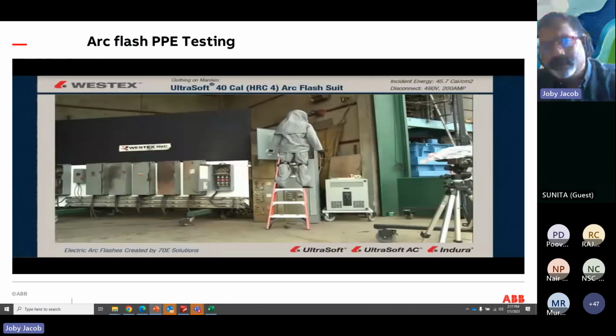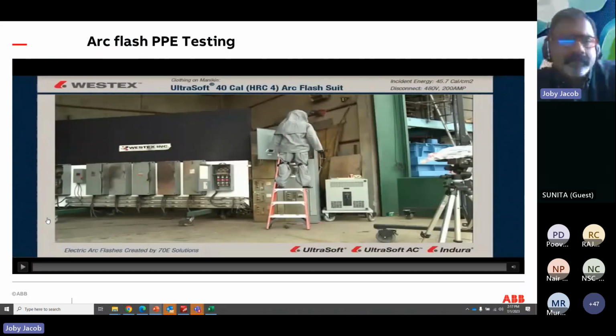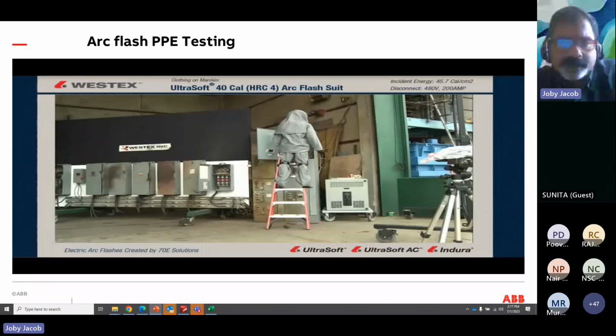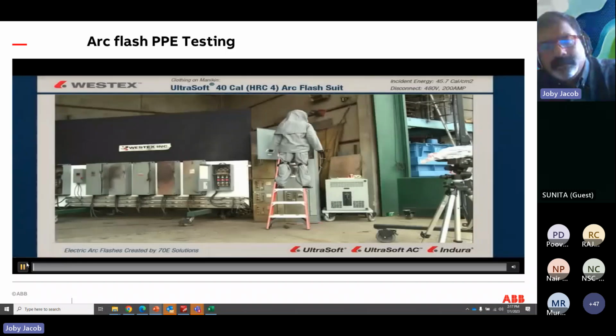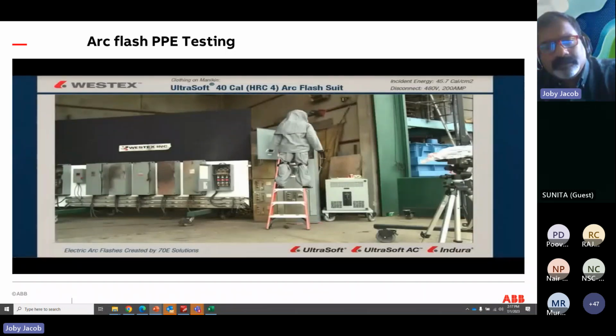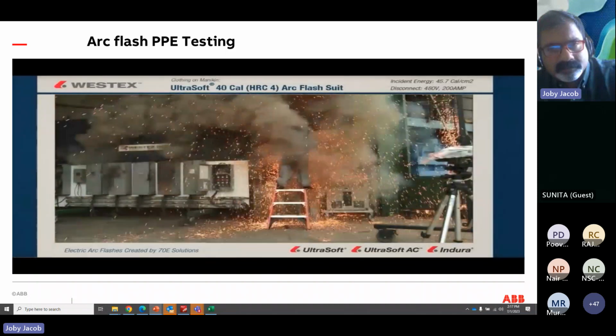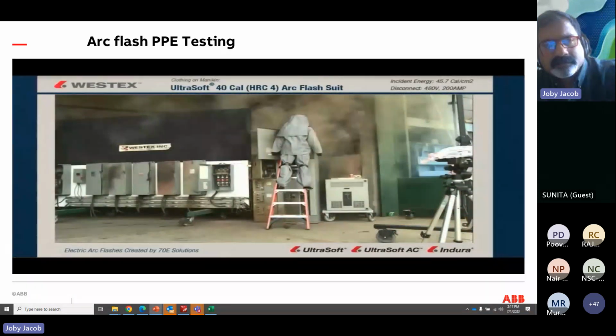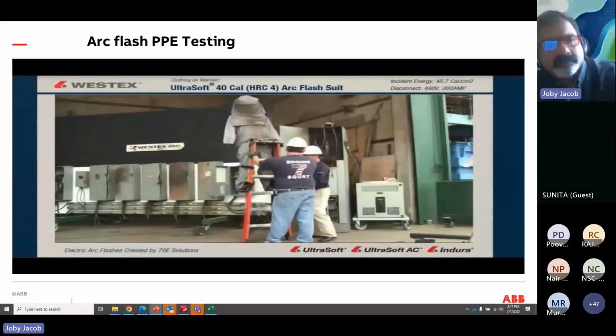I was searching for a lower category PPE, but I got this one. This is related to a 40 cal suit in front of a medium voltage switch breaker. What exactly happens when an arc flash burns? This mannequin is wearing a Westex UltraSoft 40 cal arc flash suit, and he's up on a ladder because folks asked us what happens if an electrician is up a ladder. We're faulting the upper bucket of the motor control center. It's a 40.7 calorie arc. Very large arc. There's a ton of molten metal coming out in all directions, but there is no fire on the garment. You'll see when our firefighters come in and turn the mannequin around that there's also no break open, showing that even in a 45 calorie arc, the UltraSoft provides sufficient protection.